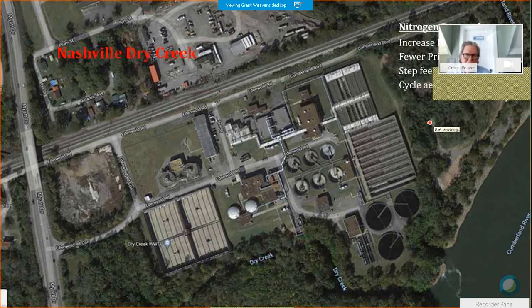This was designed with the idea, and this is pretty interesting to me anyway, not really thinking about phosphorus removal, and not really thinking about total nitrogen removal, but the design concept when those basins were built was: if we create a low oxygen zone, we're going to call that a selector. And the selector is going to select against any filaments that thrive in a high oxygen environment.